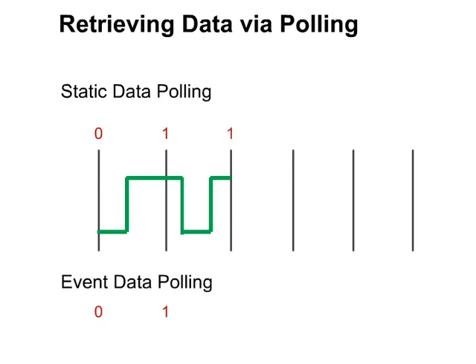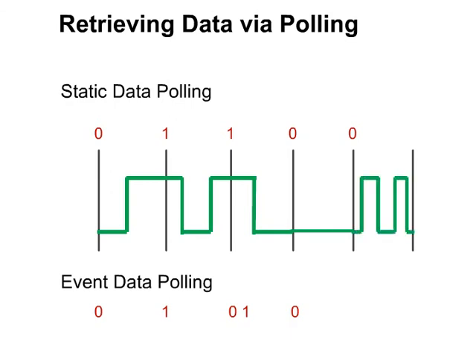During the next poll interval, the input transitions low again. With static or event polling, this transition is reported. During the next poll interval, the input does not transition. With static polling, the current state — still low — is reported. No events are reported with event polling, however, because nothing has changed. During the next poll interval, the input transitions high, low, then high, and then low again. With static polling, only the current state — low — is reported and all of the transitions have been lost. With event polling, however, each of these transitions are reported.